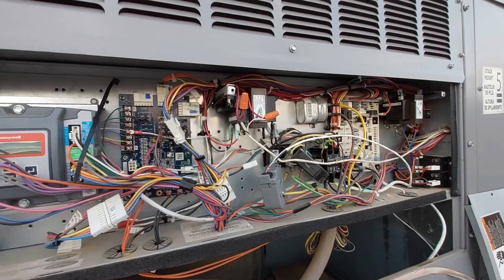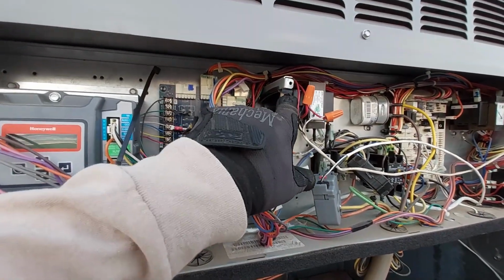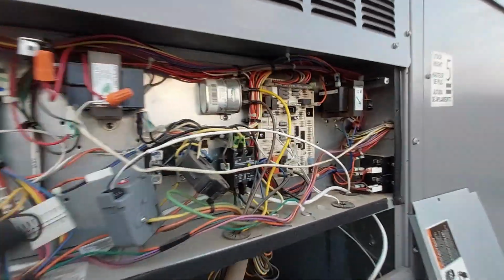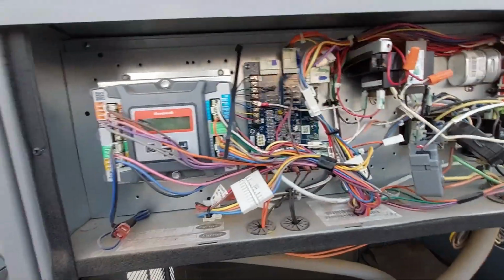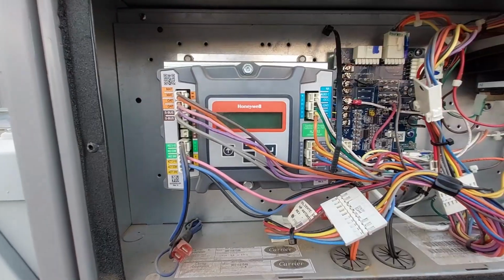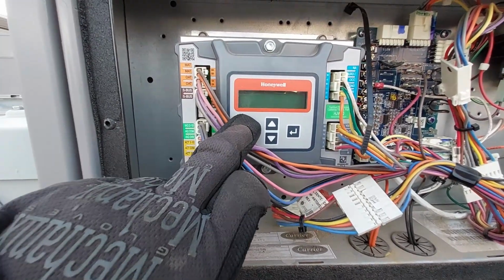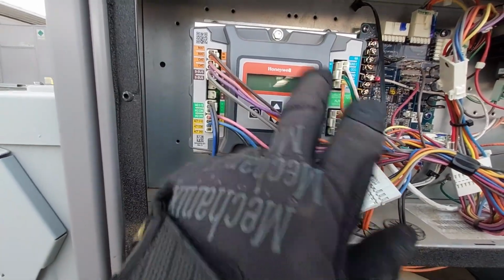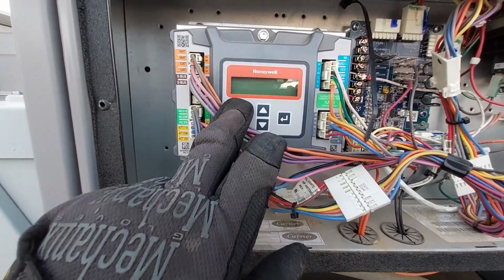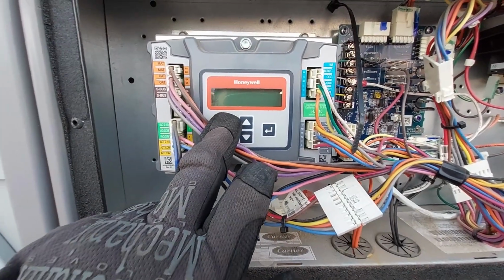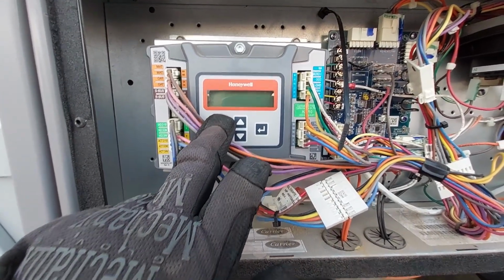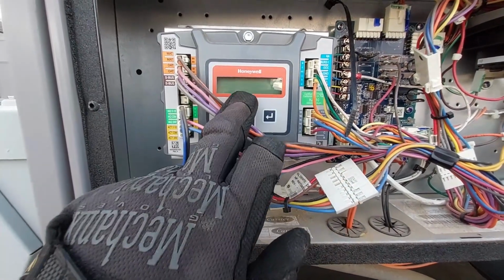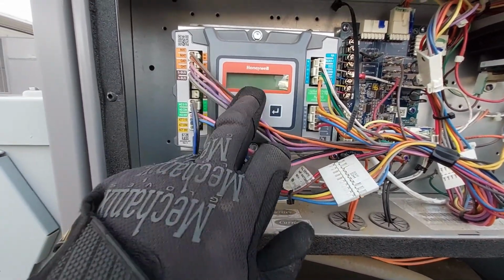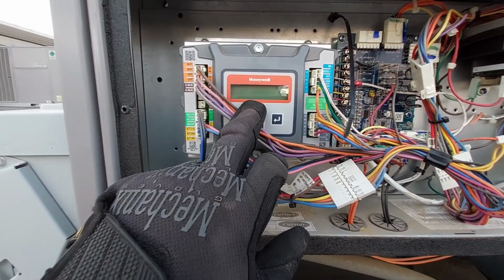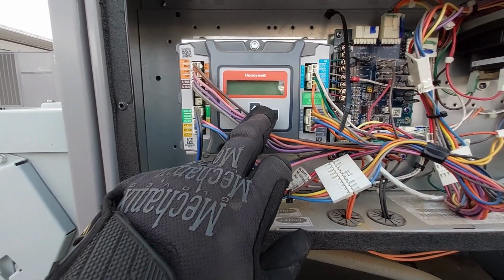I checked my transformers. They're not popped, right? They're good. So this one's pretty good too. And that's when I noticed that this Honeywell board is completely blank. Usually it'll have something here saying either on cooling or heating or standby, but right now it's completely blank, which kind of is throwing up some red flags for me. I'm thinking that something's going on here. This wouldn't be the first time that I had a Honeywell board go bad on me.